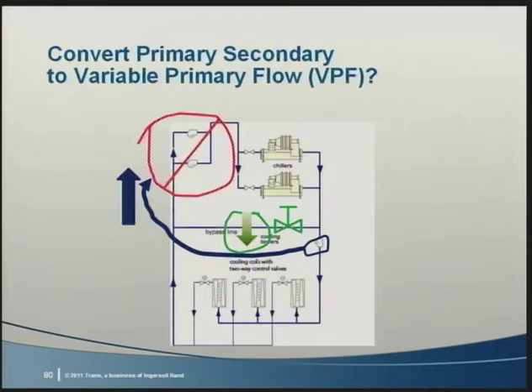In addition, we need to add a way to monitor chiller flow rate, either a flow meter or DP equated to flow rate for each chiller. That's a lot to do and basically requires reconstruction of the system. So, does anybody retrofit from primary-secondary to VPF? Sure. With all the changes, why?